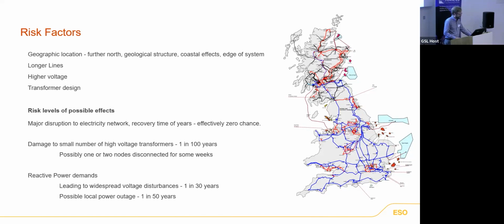So, risk levels and possible effects. We think having a major disruption to the electricity network with a recovery time of years is not really a realistic scenario - effectively zero chance of that when we're talking about GIC and our reasonable worst case scenario of a 1 in 100-year event. In a 100-year event, we'd expect to see damage to a small number of high voltage transformers, which could possibly lead to 1 or 2 nodes on the network being disconnected. But if that happened, we think there are spares available that we could mobilize to get those nodes back on service relatively quickly.